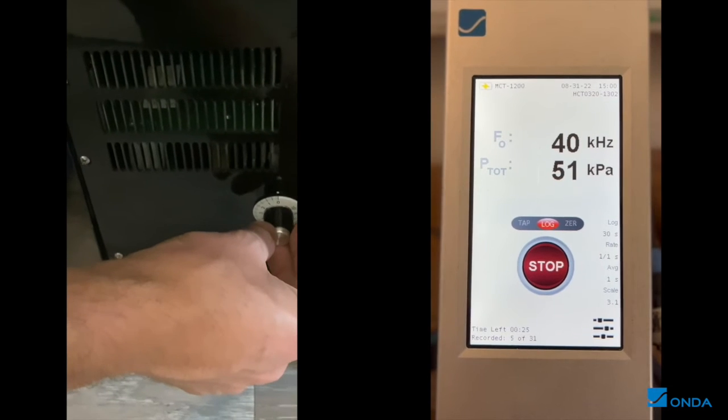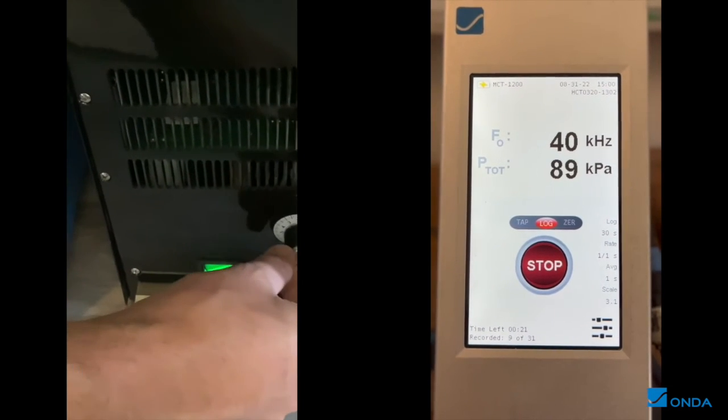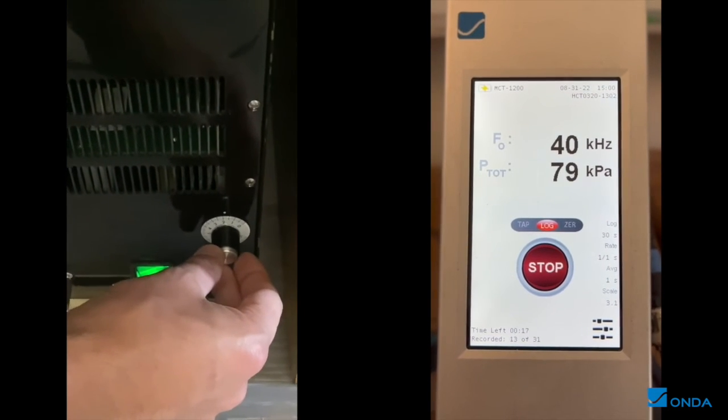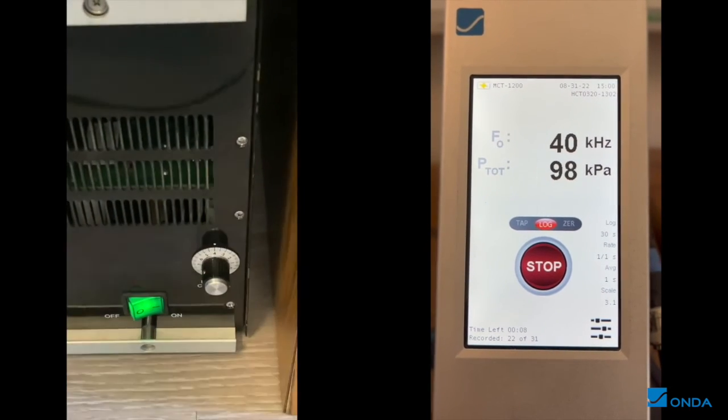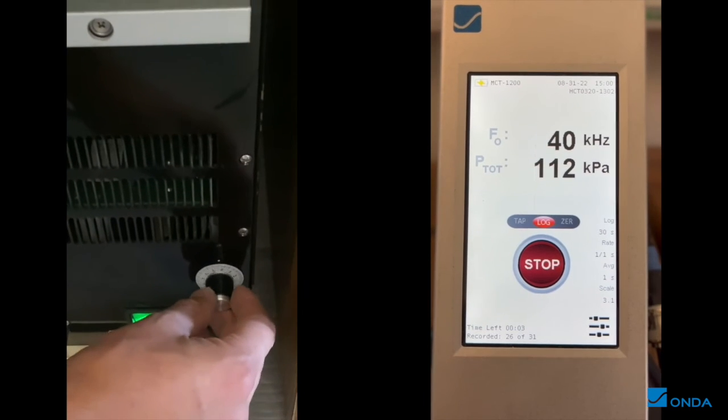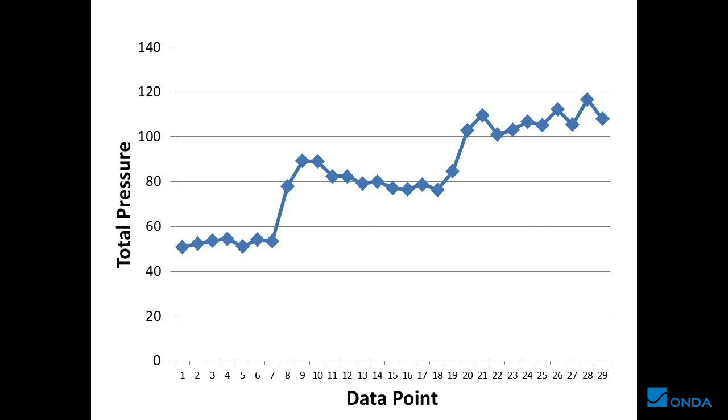You are now ready to continuously monitor the acoustic output in your cleaning tank. You will notice that as we change the generator power, the acoustic pressure measurements also change. Detecting real-time process excursions is now possible.